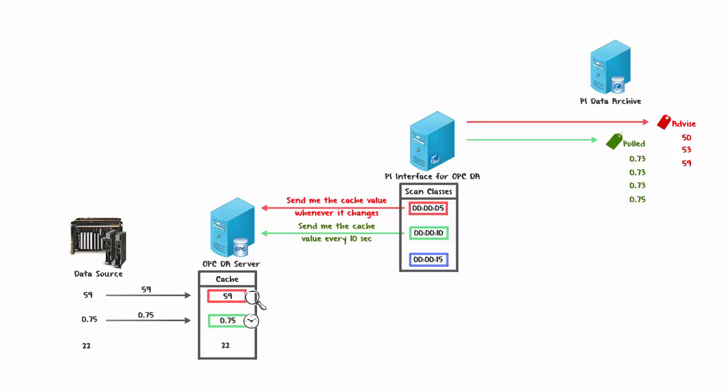For the last Scan Class, if the PI Interface for OPC DA finds an Event Point, it won't do anything immediately, because for every Event Point there's a trigger point defined. It's only when this trigger point gets a new value that the PI Interface makes a request to the OPC Server — asking it to scan the device directly for a new value, bypassing the cache. This value is then sent to the Event Point, making it ideal for cases where a PI Point should only receive values when another PI Point on the PI Data Archive gets a new value.